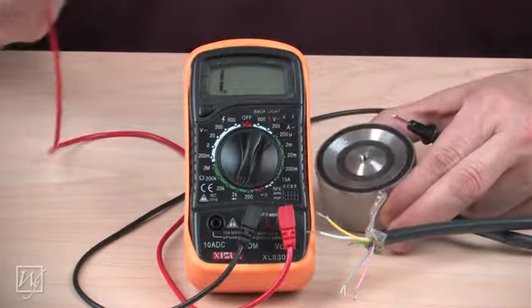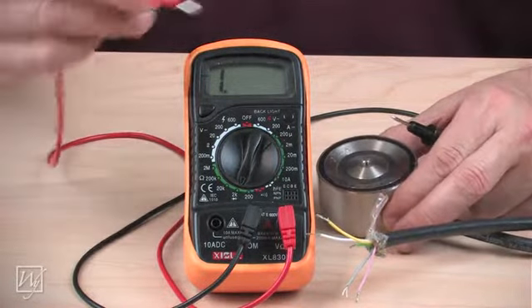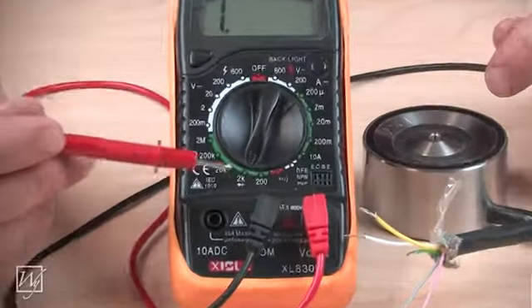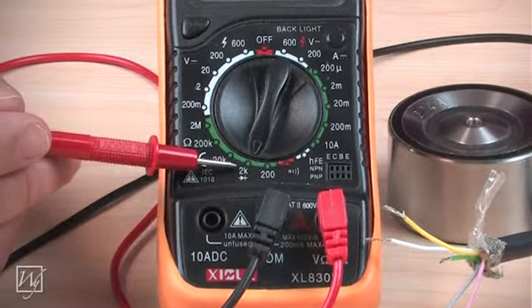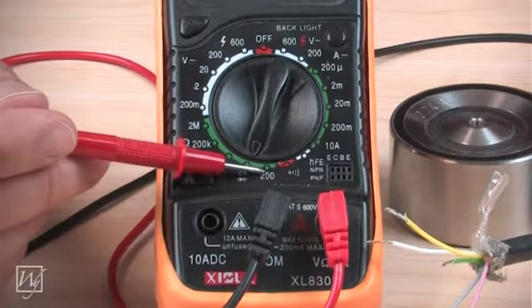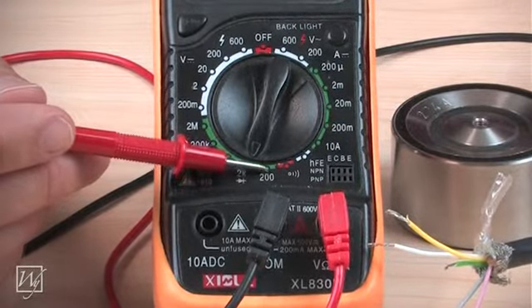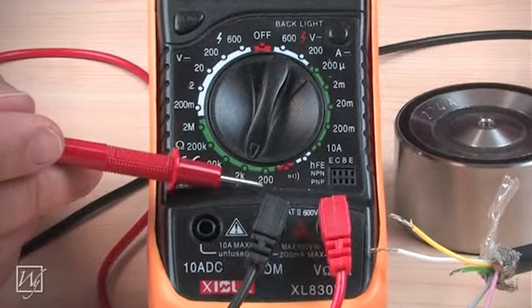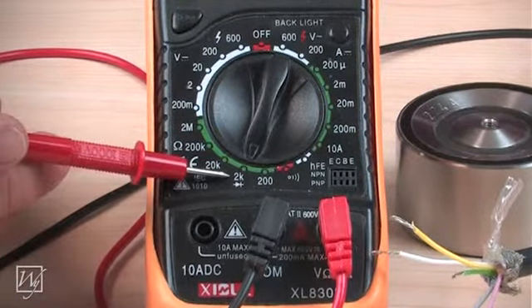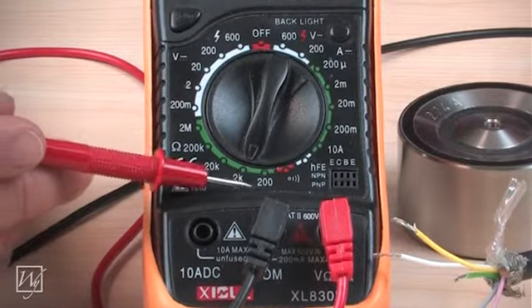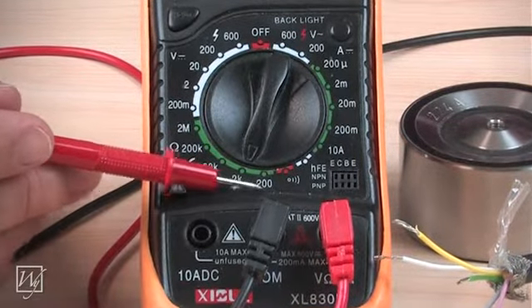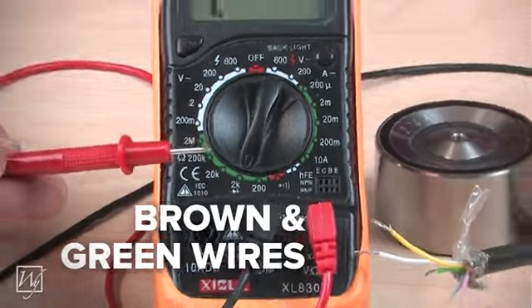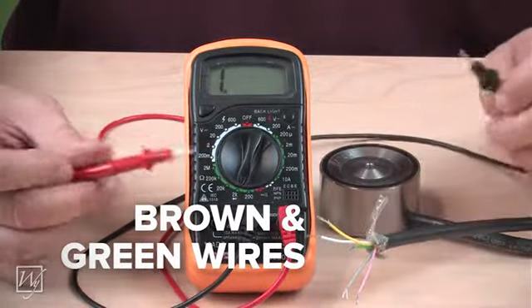We should get about 224 ohms on this sensor and if you look here we have a 200 range and a 2k range. If we set this for 200, since the reading is 224 it won't display. Anything over 200 will show as nothing. So we need to bump it up to the 2000 range so it can display numbers between 200 and 2000. So what I'm going to do now is test the heating element by testing across the brown and the green wires.